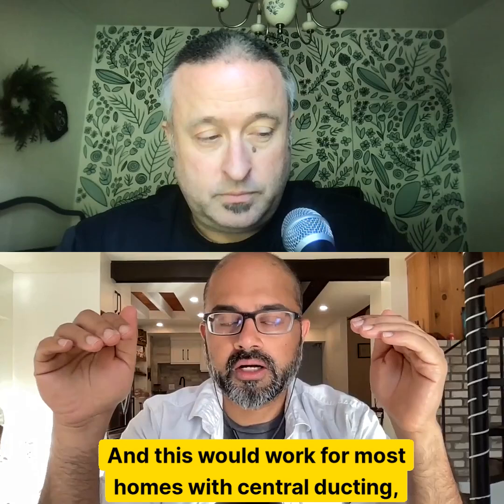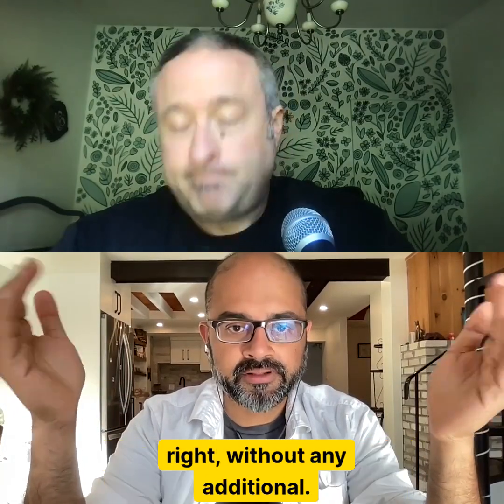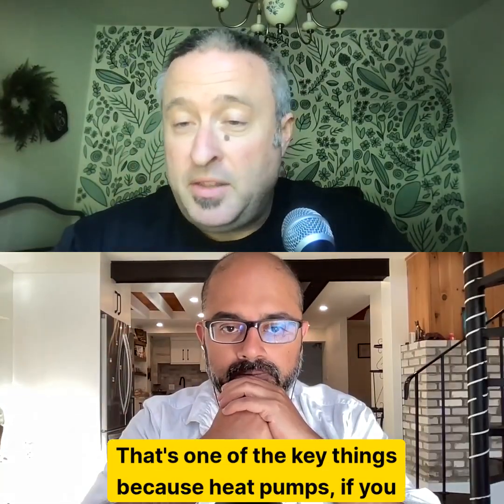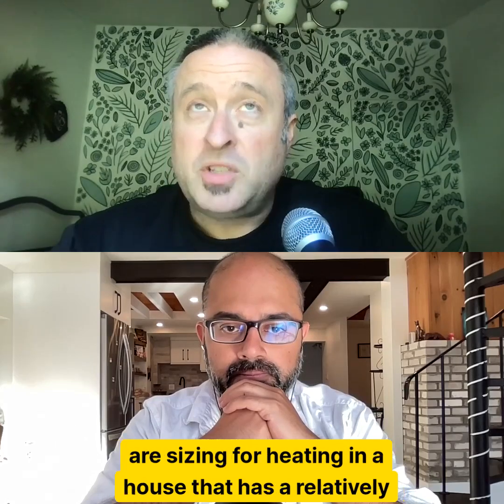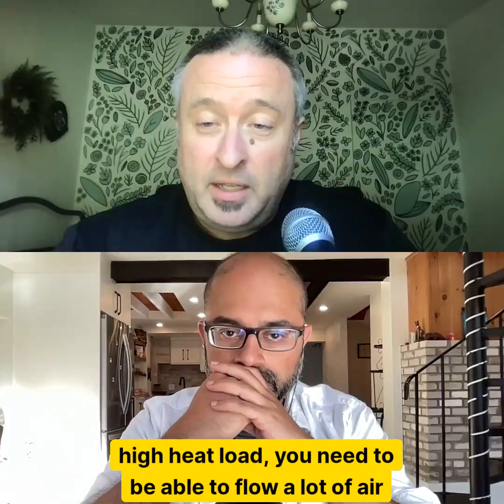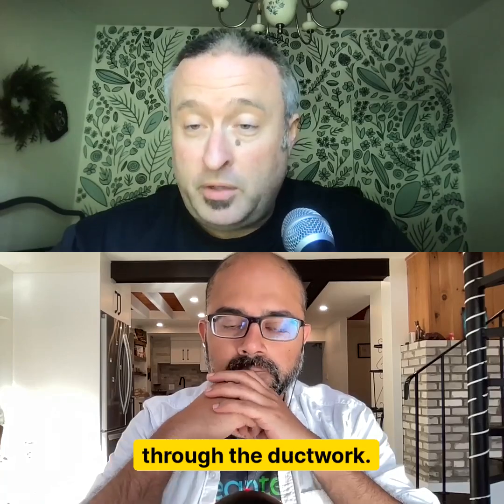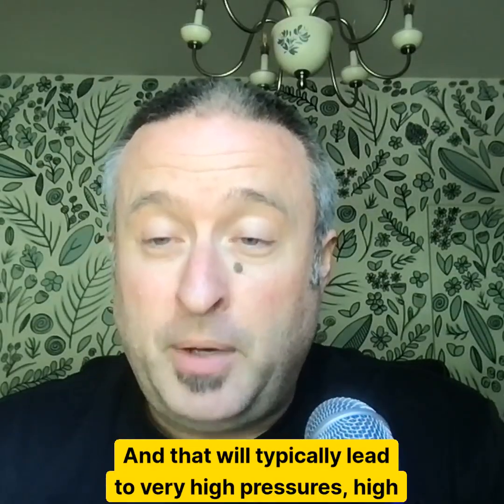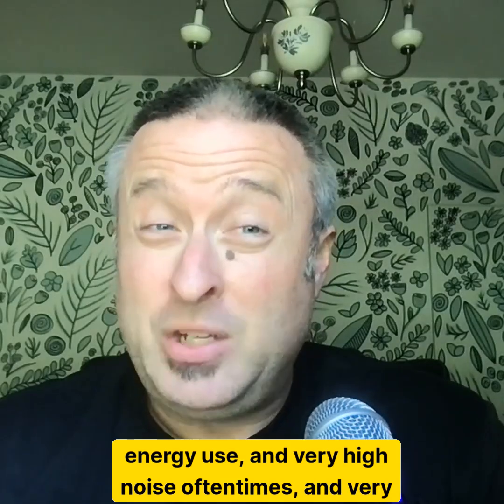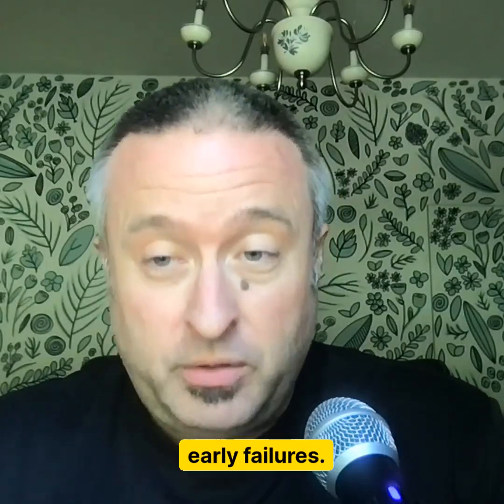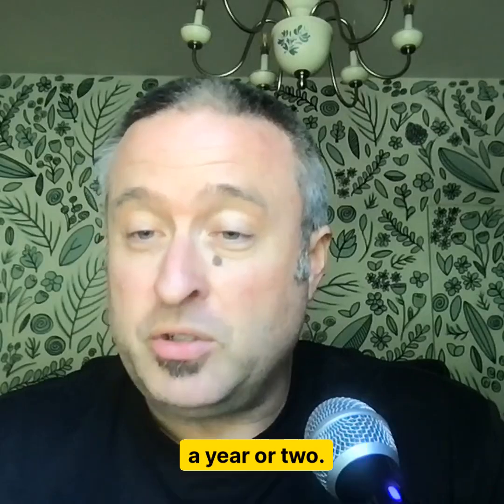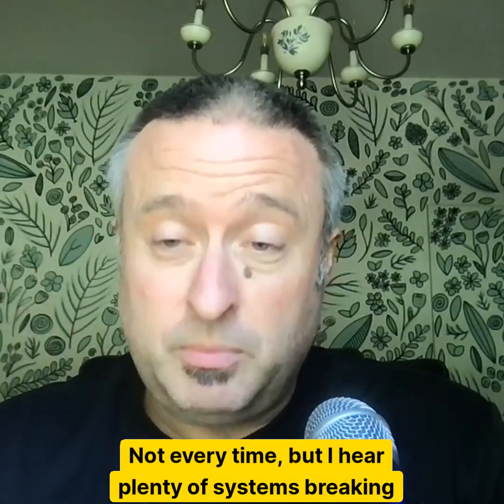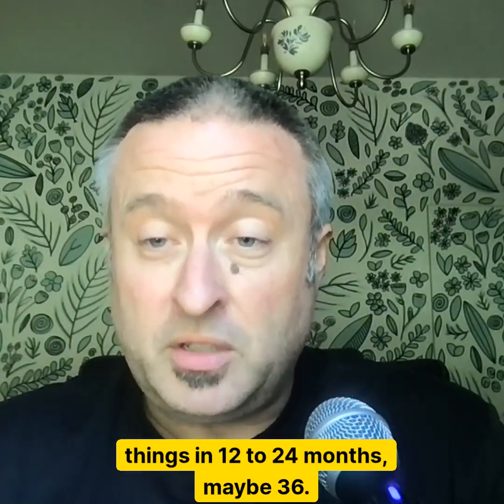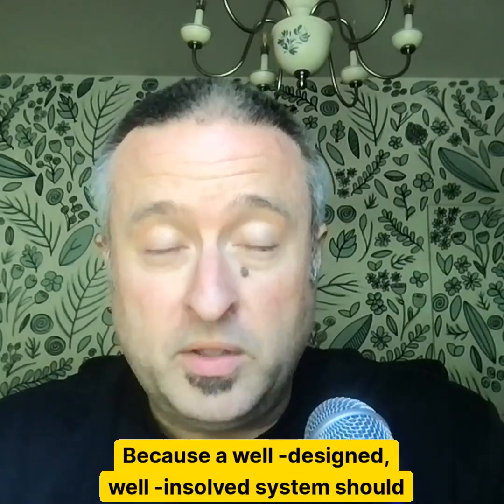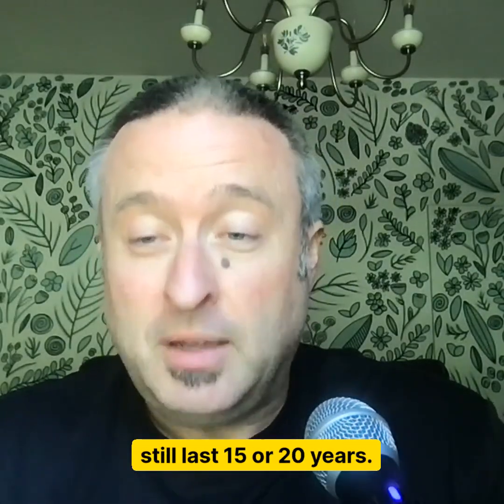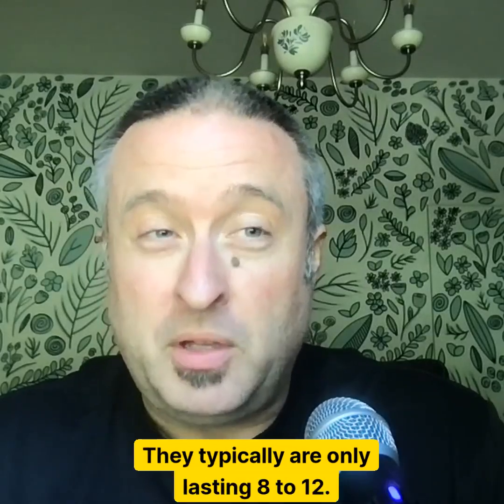And this would work for most homes with central ducting, right, without any additional work? Precisely. That's one of the key things, because if you are sizing a heat pump for heating in a house that has a relatively high heat load, you need to be able to flow a lot of air through the ductwork. And that will typically lead to very high pressures, high energy use, and very high noise, oftentimes, and very early failures. You can start losing components of the systems in a year or two. Not every time, but I hear of plenty of systems breaking things in 12 to 24 months, maybe 36. That's not good, because a well-designed, well-installed system should still last 15 or 20 years. They typically are only lasting 8 to 12.